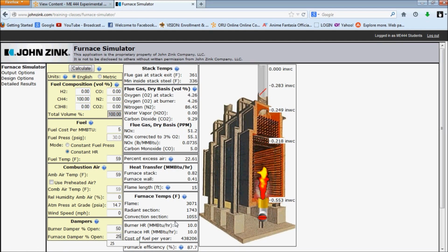So let's try cutting the furnace damper in half again, so 50 and 25. Alright, so now our oxygen is actually lower than what we expected, and the draft is actually getting closer. It's not 0.2 anymore, but 0.08, which is pretty close to our 0.05 that we want. But I still think we can get closer, so let's try changing 25 to 26 to kind of get the oxygen up.